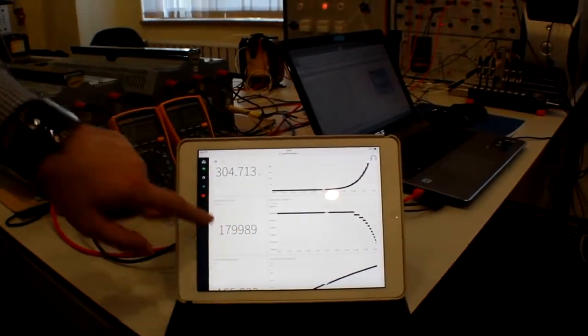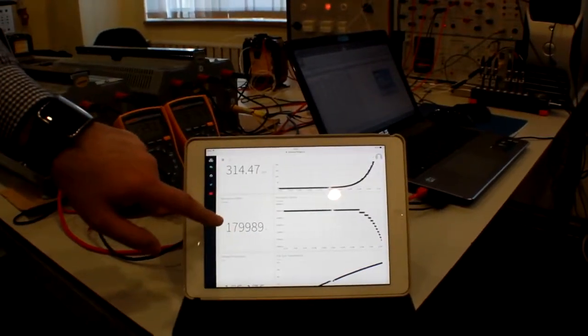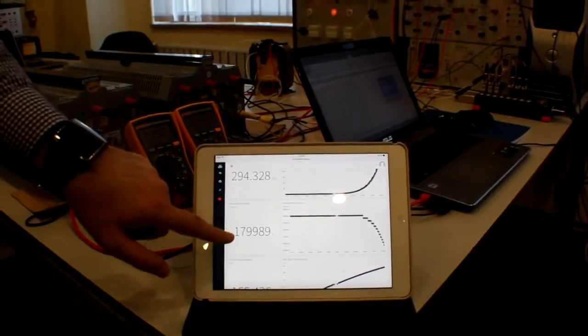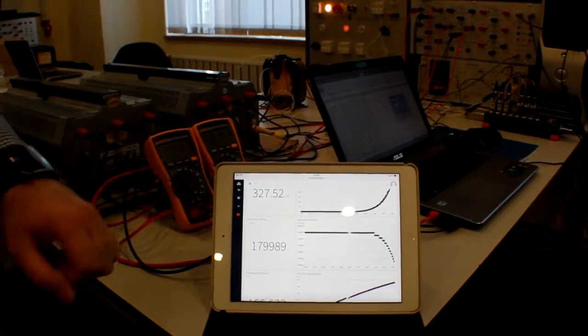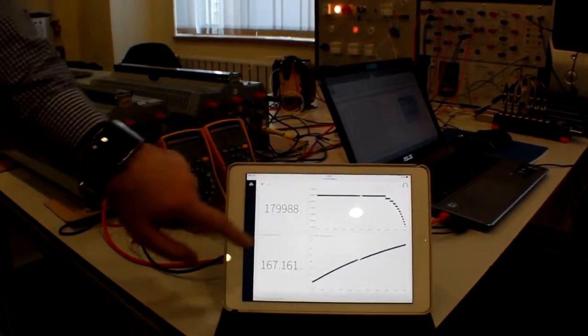And this is the remaining life for the transformer. After 4 hours, we are expecting that this remaining life is going to become very close to 0, and after that the transformer will start to burn.